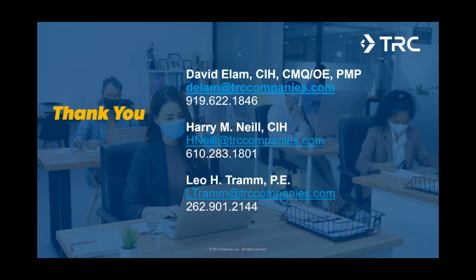Okay, great. We have one more question. What are ASHRAE's requirements for air changes per hour? ASHRAE uses different sets of units. The ASHRAE standard that we are referring to and the CDC is referring to is 62.1. And in there you'll find that ASHRAE suggests or sets a standard for outdoor air introduction and rates of cubic feet per minute per square foot of building, or cubic feet per minute per occupant or per person.